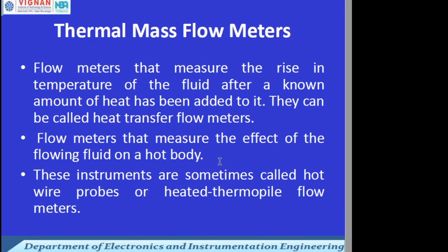The next one is the thermal mass flow meter. These flow meters measure the rise in temperature of the fluid after a known amount of heat has been added to it, so they can be called heat transfer flow meters. They measure the effect of the flowing fluid on a hot body. These instruments are sometimes called hot wire probes or heated-thermopile flow meters.